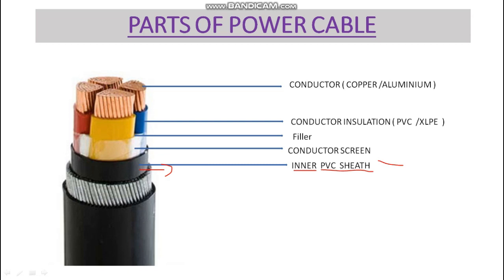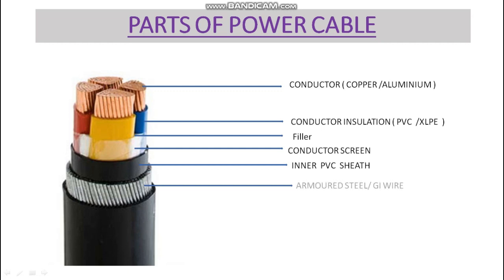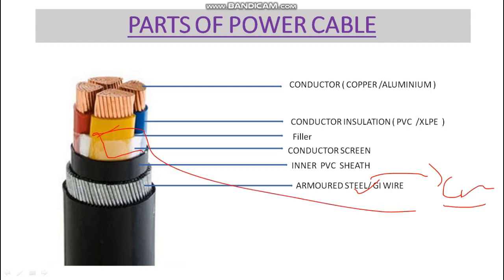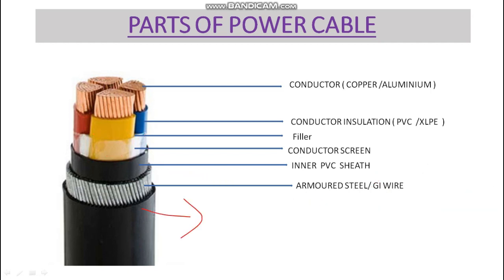Above the conductor screen we have an inner PVC cover, which is the inner sheath made of polyvinyl chloride. Above that is the armoring — it can be steel tape or GI wires, most commonly steel tape — which provides mechanical protection. Finally, there is the outer PVC sheath, which is the enclosure or outer cover.